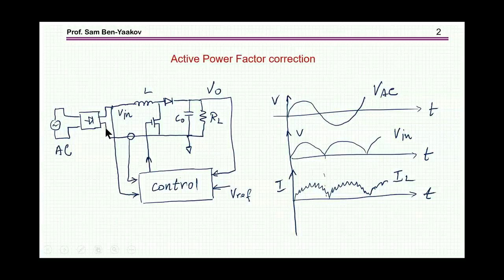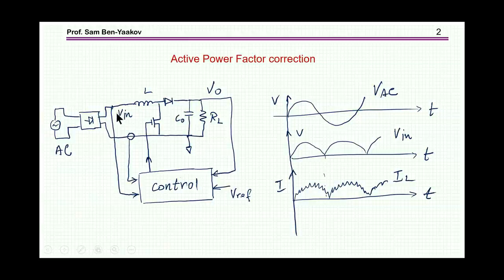In the classical approach, we'll be sensing the output in order to keep it constant, independent of load changes, sense the input voltage as a reference, and then the current of the inductor — which is actually reflected to the input as the control variable — that we are going to set to follow the sinusoidal waveform of the input.